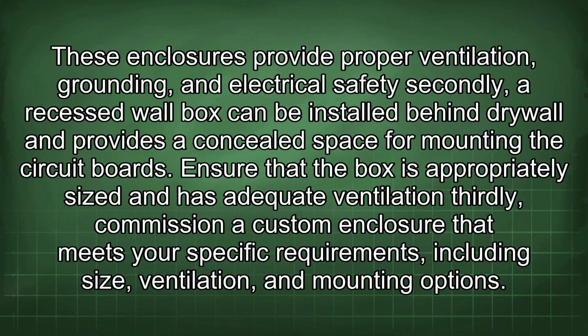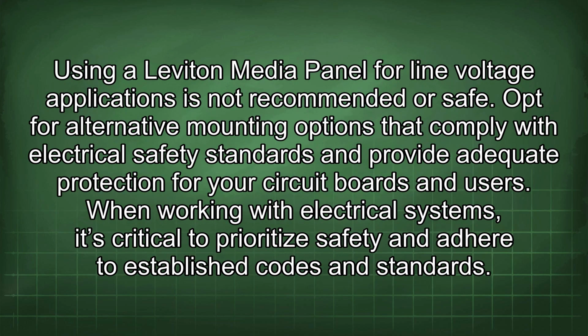Secondly, a recessed wall box can be installed behind drywall and provides a concealed space for mounting the circuit boards. Ensure that the box is appropriately sized and has adequate ventilation. Thirdly, commission a custom enclosure that meets your specific requirements, including size, ventilation, and mounting options. Using a Leviton media panel for line voltage applications is not recommended or safe.